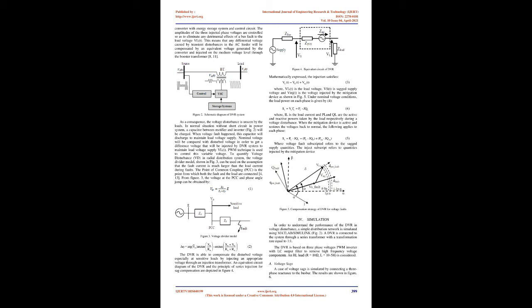Voltage source converter. A voltage source converter, VSC, is a power electronic system consisting of a storage device and switching devices, which can generate a sinusoidal voltage with any required magnitude, frequency, and phase angle. This converter injects a dynamically controlled voltage in series with the supply voltage through 3 single-phase transformers to correct the load voltage. There are 4 main types of switching devices: metal oxide semiconductor field effect transistors, MOSFET, gate turn-off thyristors, GTO, insulated gate bipolar transistors, IGBT, and integrated gate commutated thyristors, IGCT. Each type has its own benefits and drawbacks.